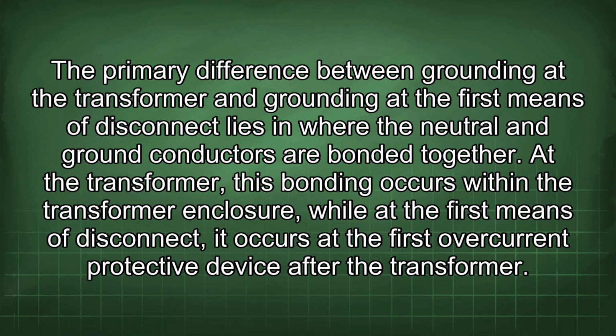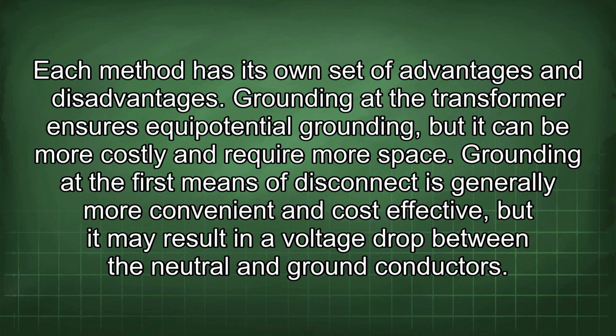The primary difference between grounding at the transformer and grounding at the first means of disconnect lies in where the neutral and ground conductors are bonded together. At the transformer, this bonding occurs within the transformer enclosure, while at the first means of disconnect, it occurs at the first overcurrent protective device after the transformer. Each method has its own set of advantages and disadvantages.